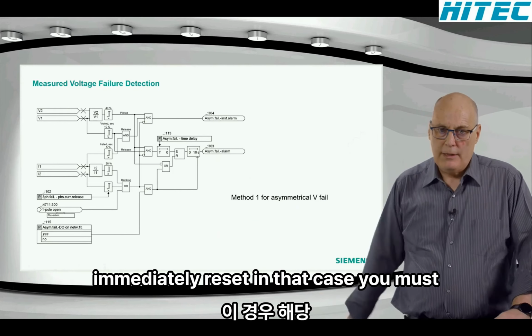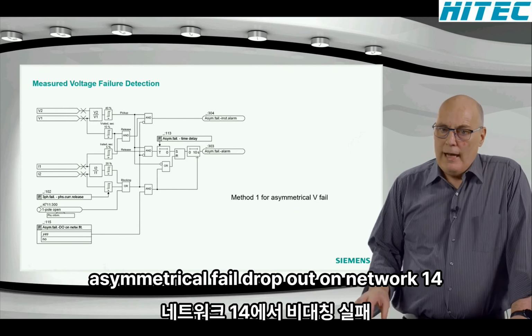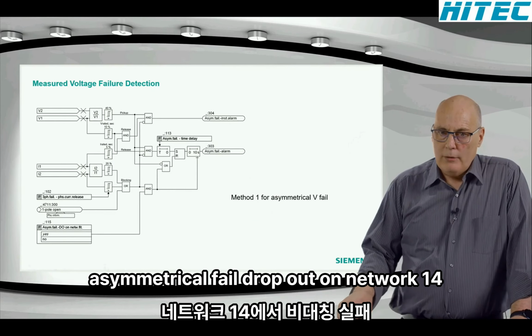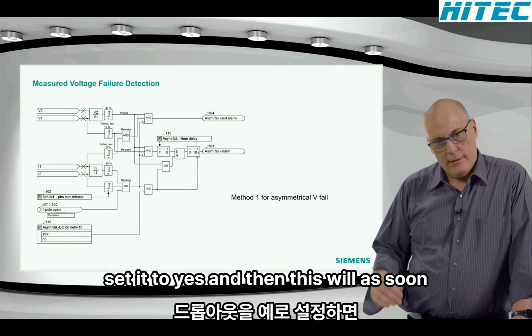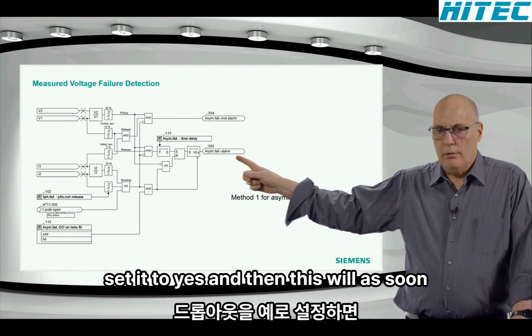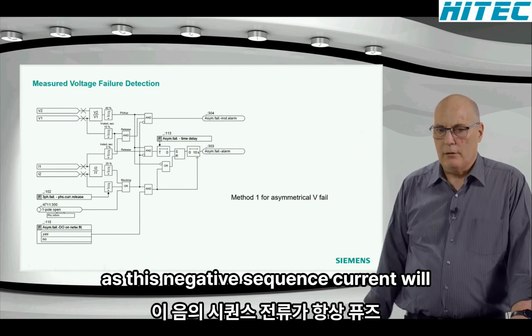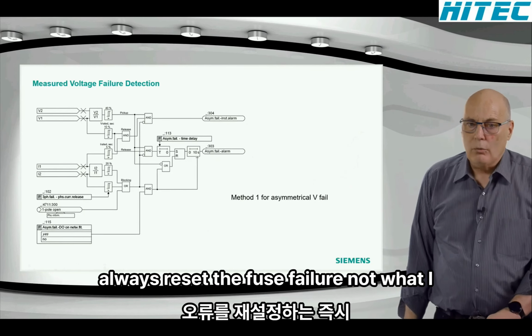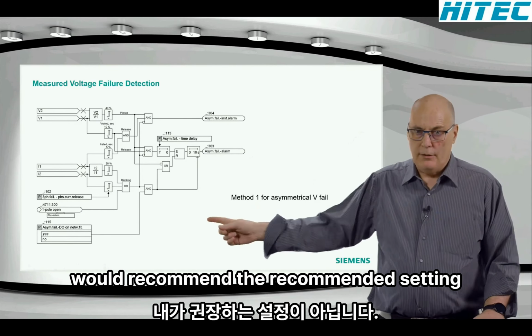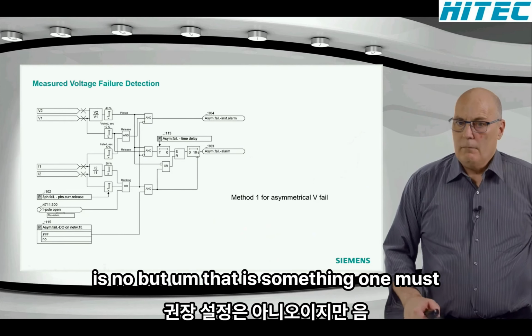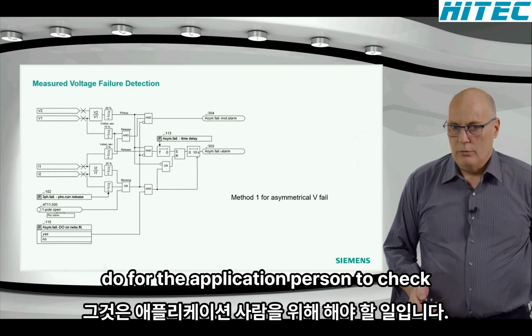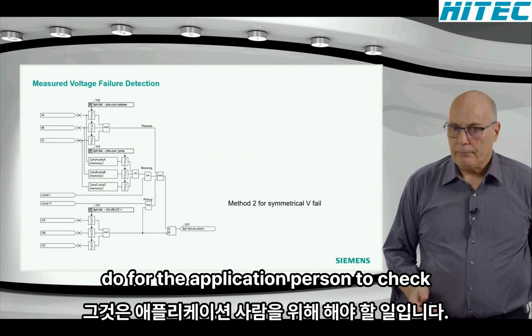In that case, you must set that parameter at the bottom there. Asymmetrical fail dropout on network fault, and you say set it to yes. Then, as soon as there's negative sequence current, this will always reset the fuse failure. Not what I would recommend. The recommended setting is no, but that is something one must do for the application person to check.